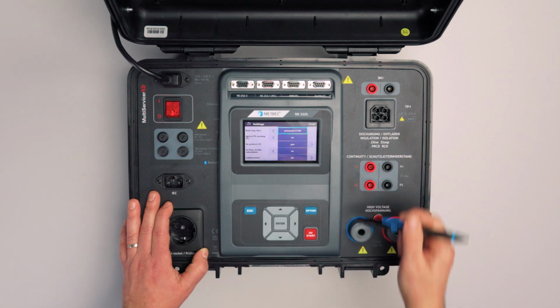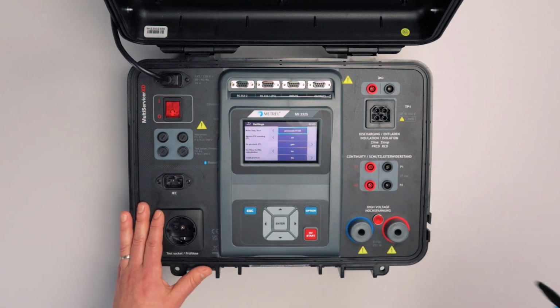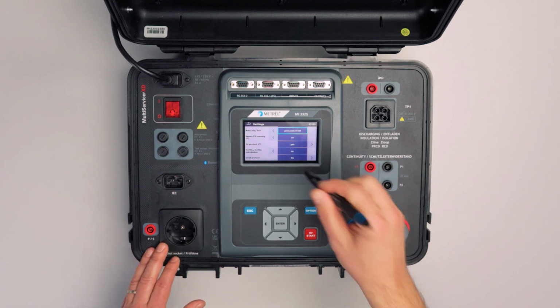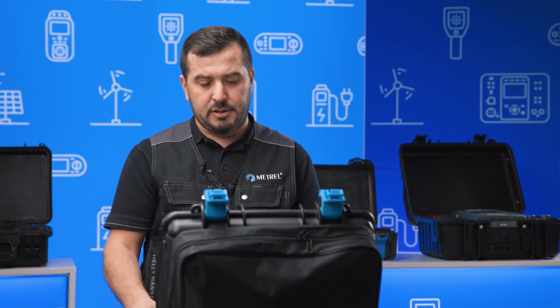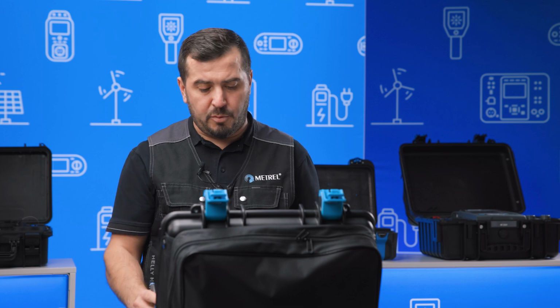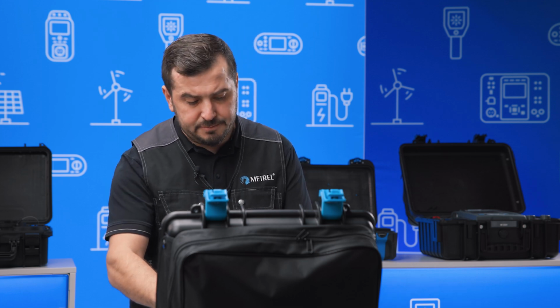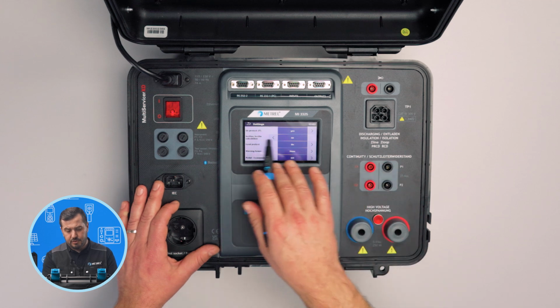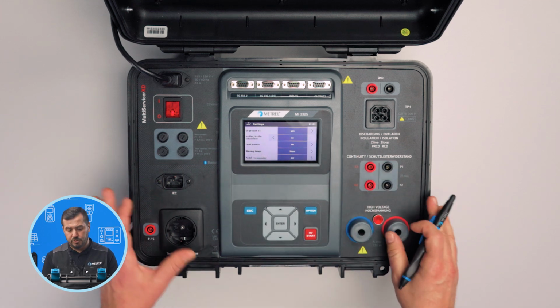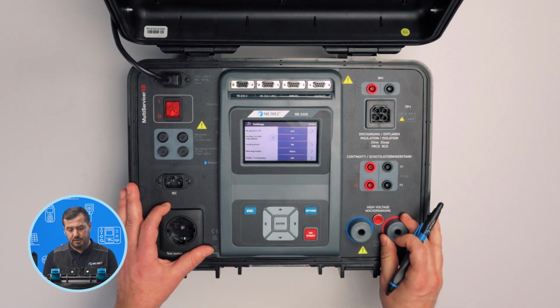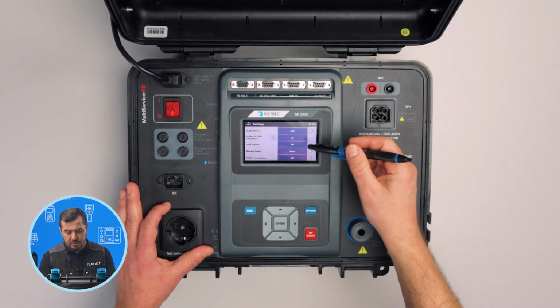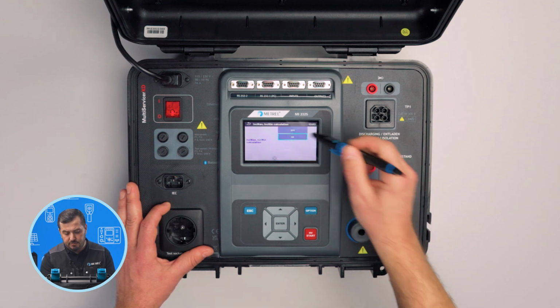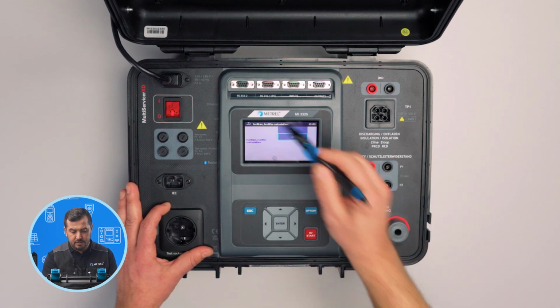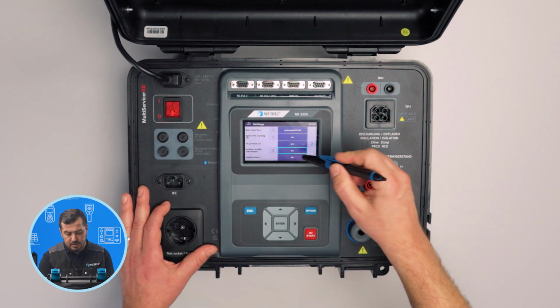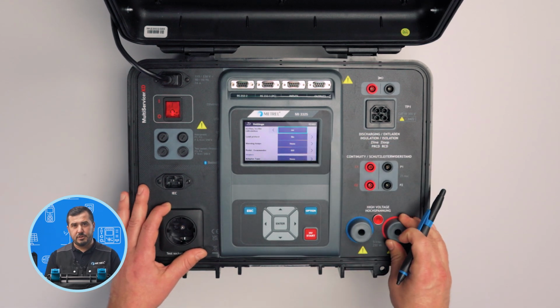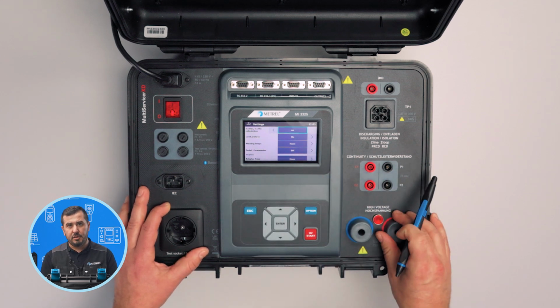Ignore PE warning. The instrument can be used also on the IT system, and we can here choose to ignore this pre-test, and it will not pop up with the warnings. Then there is an option called contact voltage pretest. This has effect on the IT system. We can decide if we want to calculate the factors.